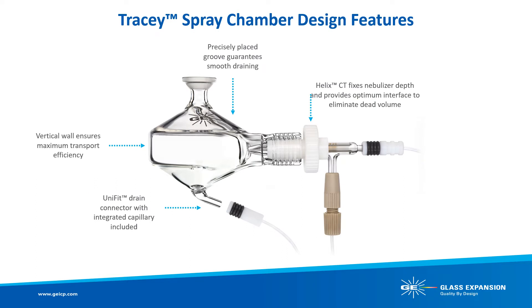Now let's take a closer look at the unique design features of Glass Expansion's Tracey cyclonic spray chamber. The design helps ICP analysts achieve sensitivity gains, reduced washout times, and reduced matrix effects not possible with other designs. An indented groove built into the top of the spray chamber serves as a barrier preventing solution from being swept into the torch — the position and depth of this groove are critical. The Helix CT fitting is carefully designed to fix the depth of penetration and torque of the nebulizer seal so that the aerosol produced is optimal, and it is the only true zero dead volume nebulizer-spray chamber interface providing unmatched washout efficiency.